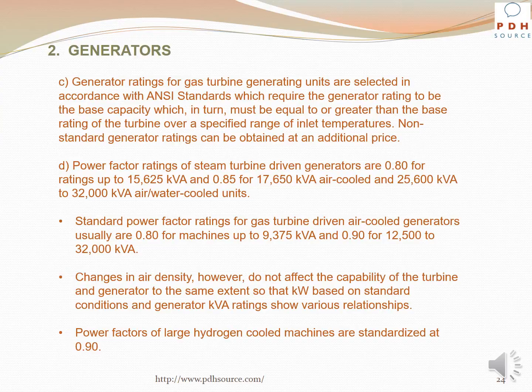Power factor ratings of steam turbine driven generators are 0.80 for ratings up to 15,625 kVA and 0.85 for 17,650 kVA air-cooled and 25,600 kVA to 32,000 kVA air or water-cooled units. Standard power factor ratings for gas turbine driven air-cooled generators usually are 0.8 for machines up to 9,375 kVA and 0.90 for 12,500 to 32,000 kVA.